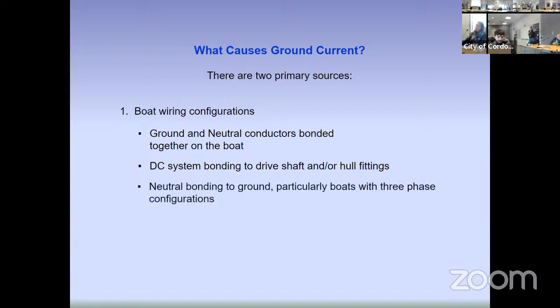And then the third one in this category, and this is particularly for the larger boats that have generators, oftentimes they will have their neutral bonded to ground, which they need to do, but the neutral is a solid connection to shore when they connect in, and that creates a circulating current into the water. Okay, one more here. The other fault condition is feeders that might fault. It affects the boats in some manner because the boats become a return path for ground current. It is where cables are chafing on the floats and they're in the water, things like that, where it might cause some ground current, a leakage.